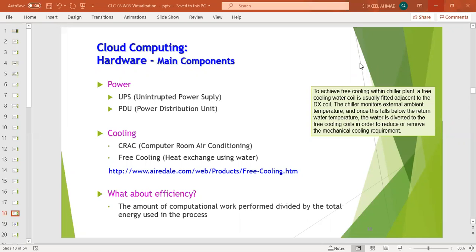Then there is the option of free cooling, that is heat exchange using water. To achieve free cooling within a chiller plant, a free cooling water coil is usually fitted adjacent to the DX coil. The chiller monitors external ambient temperature, and once this falls below the return water temperature, the water is diverted to the free cooling coils in order to reduce or remove the mechanical cooling requirements.